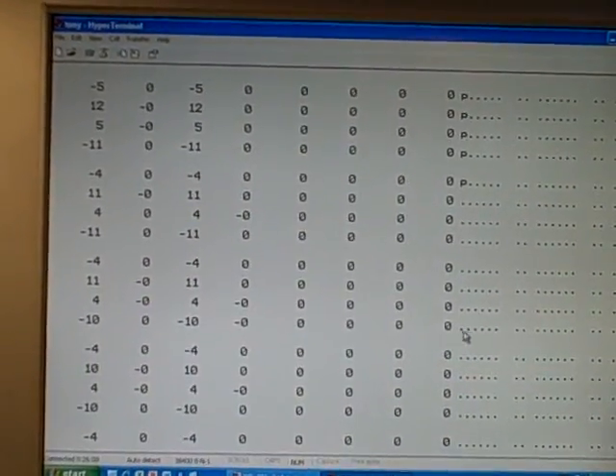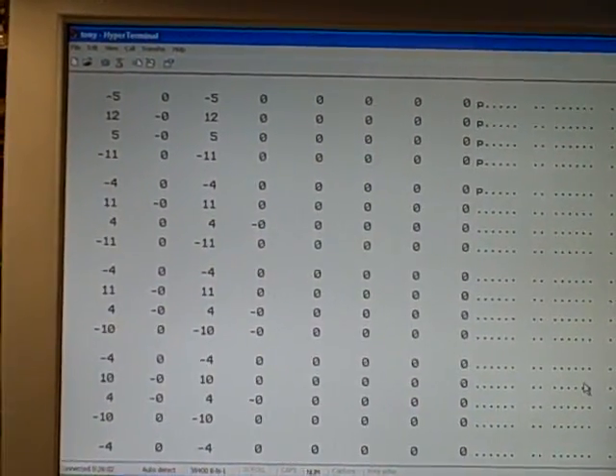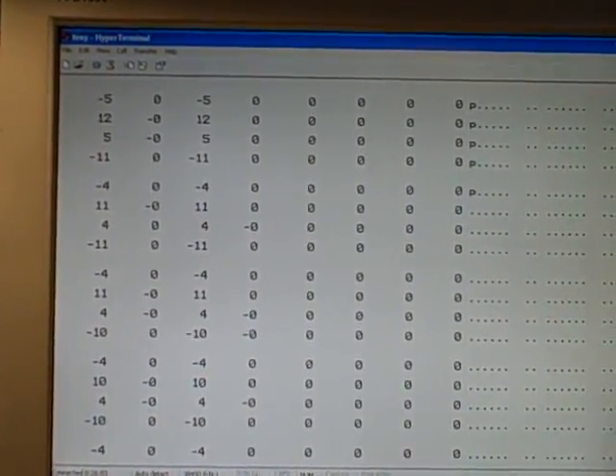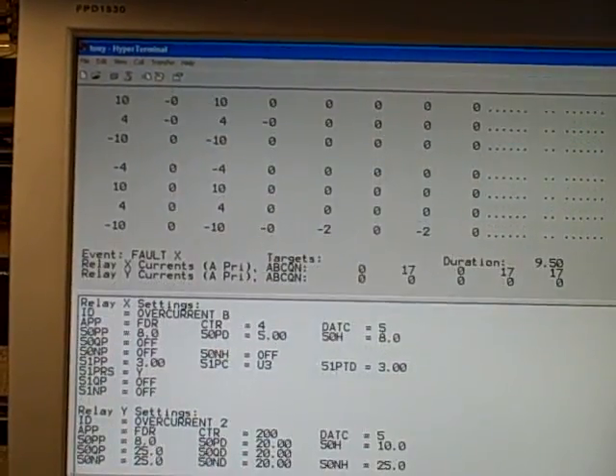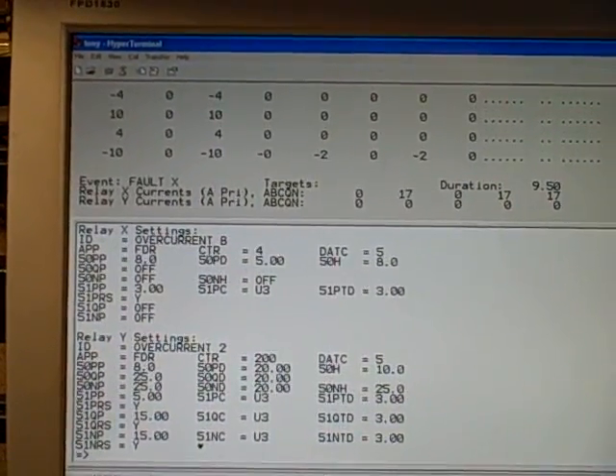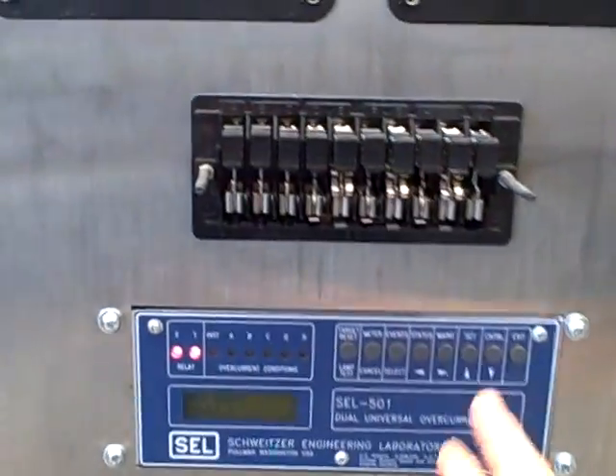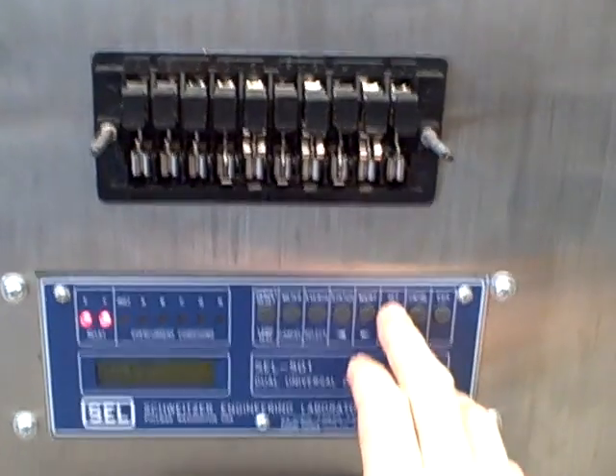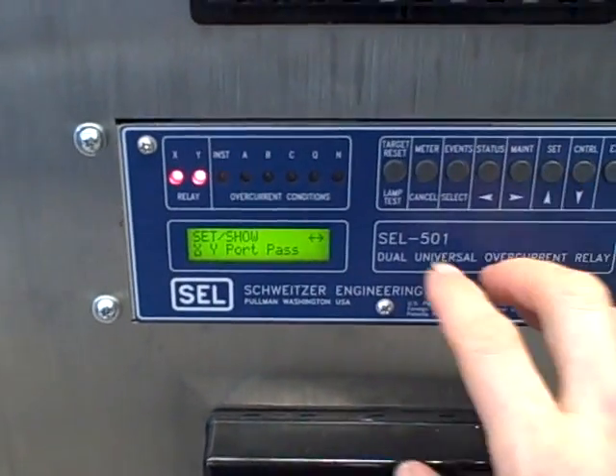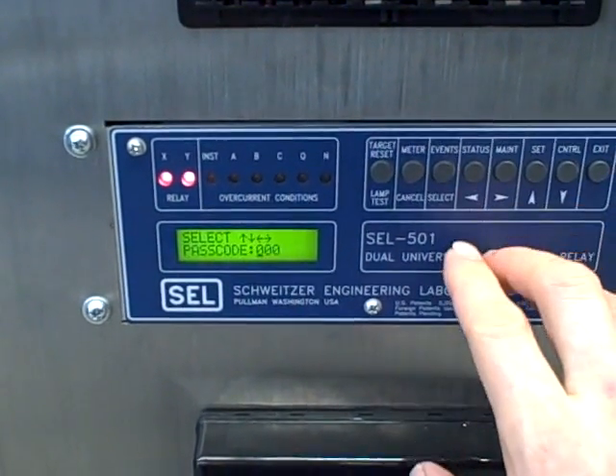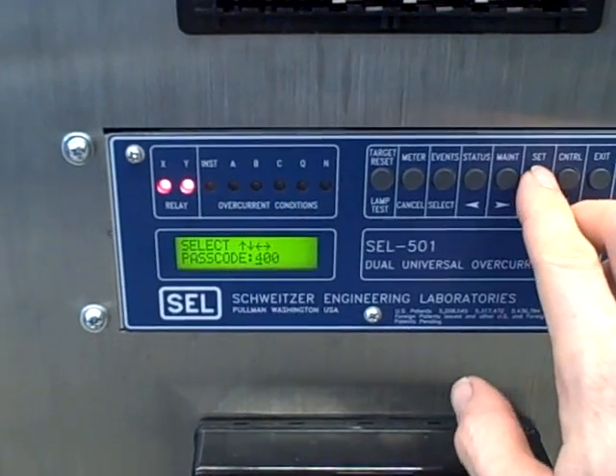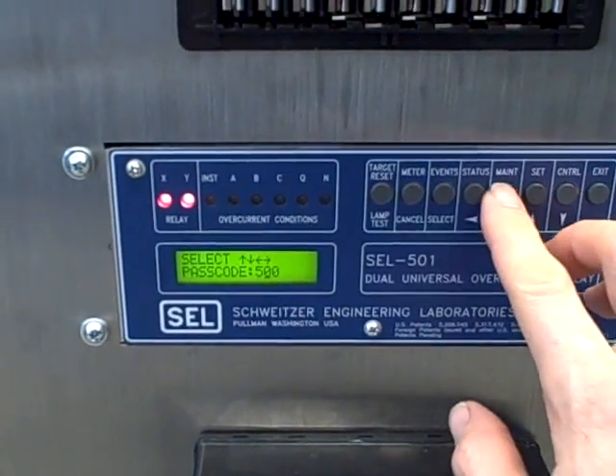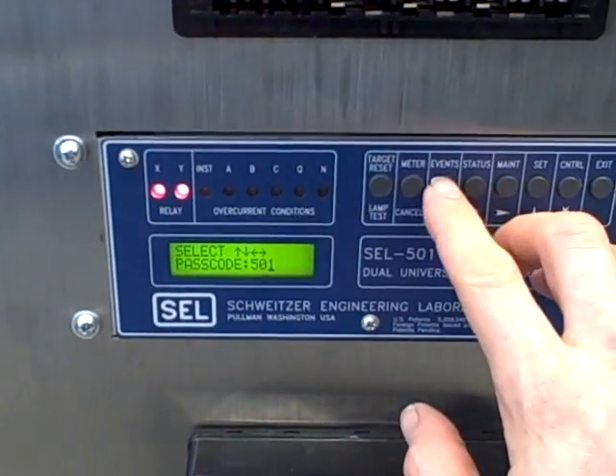So the event that we saw reported by the relay was not a trip event, but it did pick up on the 51P time over current element. So let's see what happens if we actually do have a trip event. I'm going to go over here to our relay and make a settings change. I'm going to set relay X, enter my passcode 501 by default, model number of the relay.